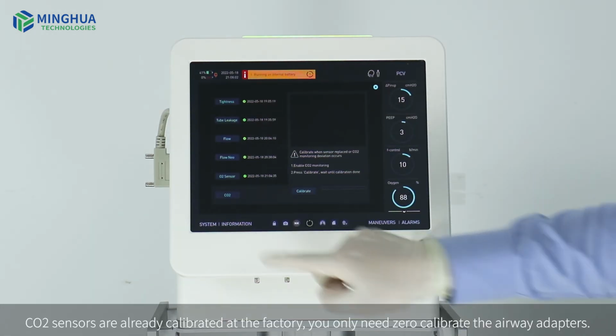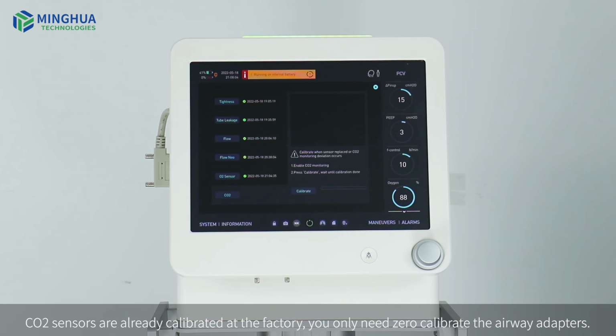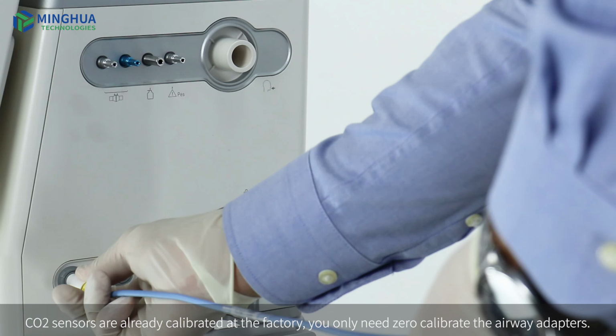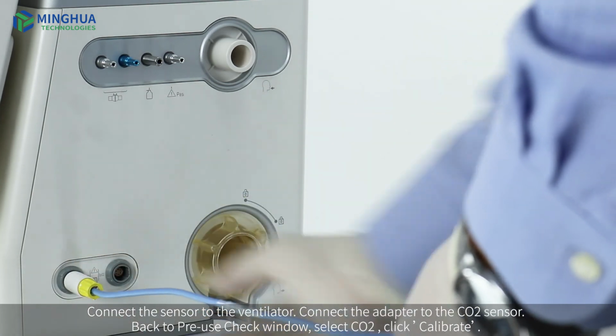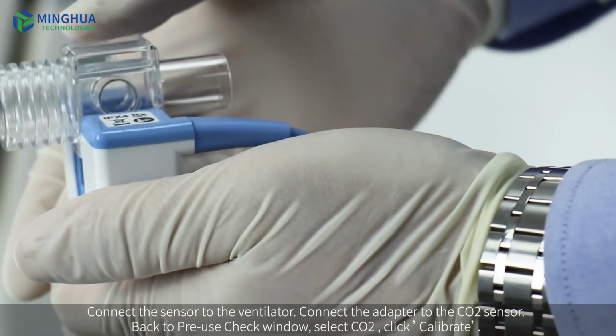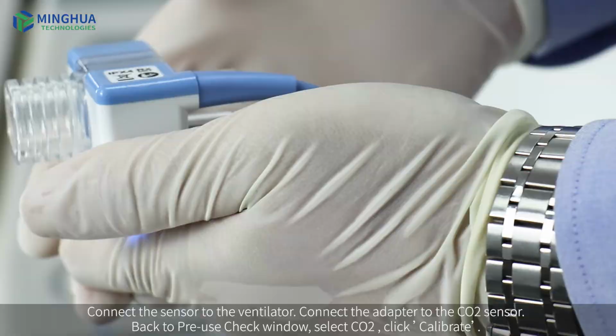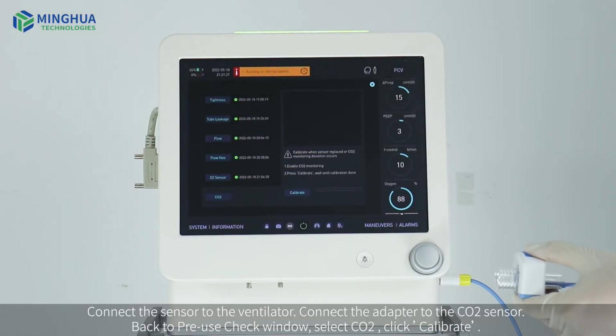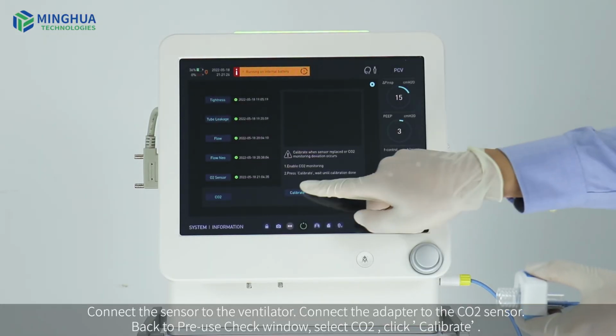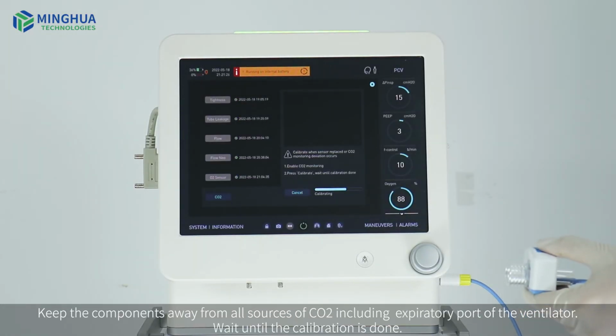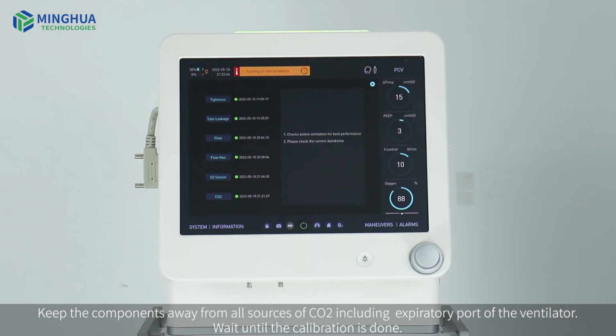CO2 sensors are already calibrated at the factory. You only need to calibrate the airway adapters. Connect the sensor to the ventilator. Connect the adapter to the CO2 sensor. Back to pre-use check window. Click Calibrate. Keep the components away from all sources of CO2, including expiratory port of the ventilator. Wait until the calibration is done.